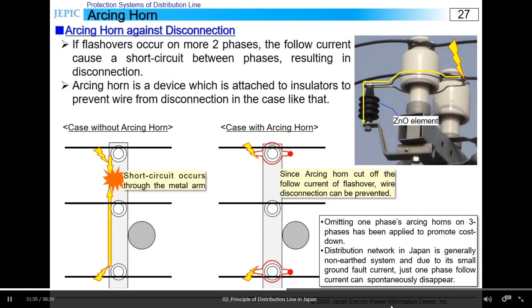This slide explains how an arcing horn works to prevent wire disconnection by flashover. Ground wire and lightning arresters are to protect the entire equipment of distribution line from lightning surge by releasing the surge to the ground. On the other hand, an arcing horn is mainly to prevent disconnection of lines by flashover. If lightning surges invade conductors and flashover between conductors and metal arm occurred on more than two phases, the follow current of flashover might transit to a short circuit through the metal arm, resulting in disconnection.